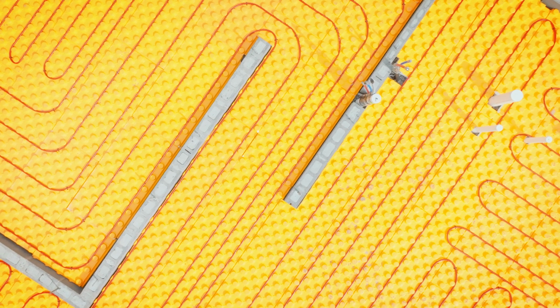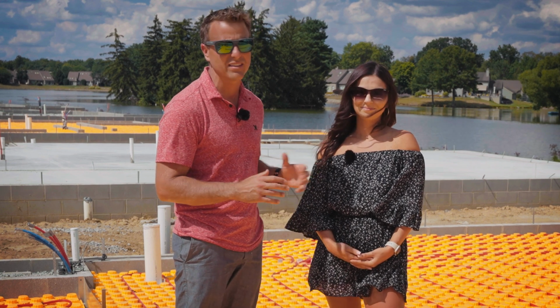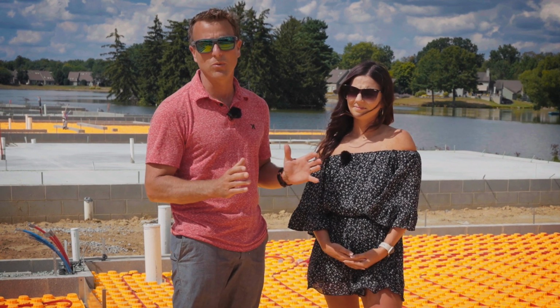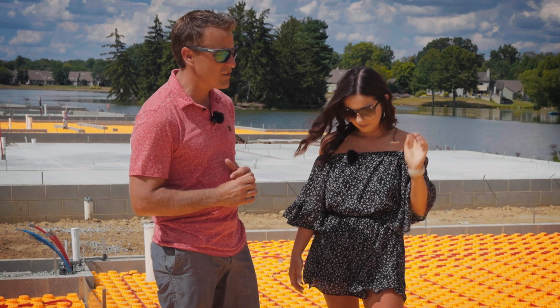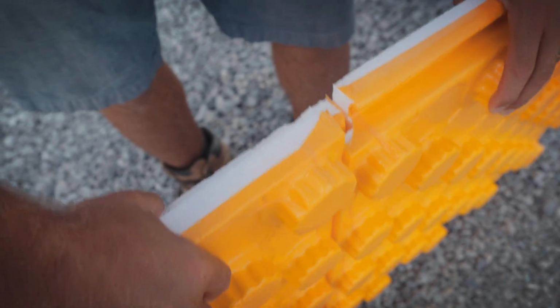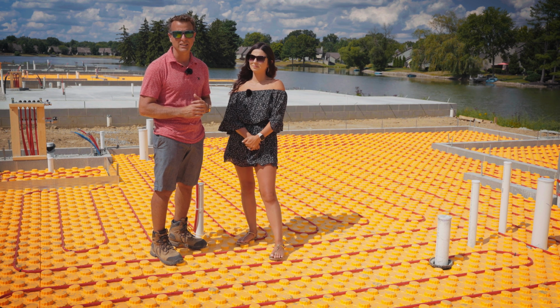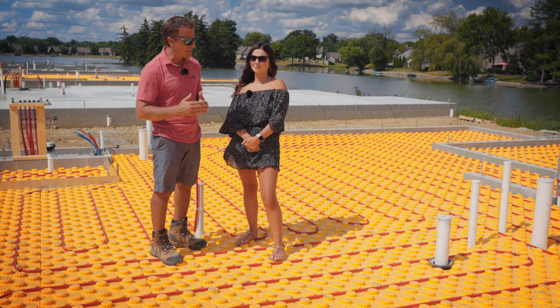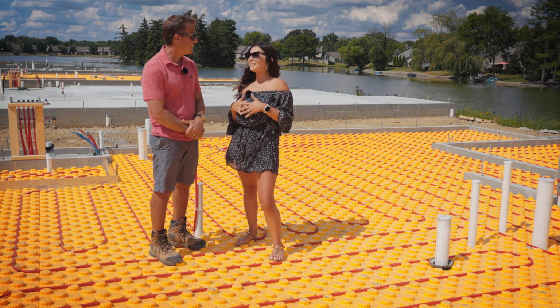Here at Arrowhead One, we have 5 loops, and one of those loops has the master bathroom and laundry room on one zone, allowing us to keep those rooms with comfort year-round. We have about 1,500 linear feet of half-inch PEX tubing on 2-inch Creatherm foam panels, providing a vapor barrier, excellent compression strength, and high-capacity insulation. They actually provide channels as well to keep the PEX tubing spaced evenly. In-floor heating is a complete game changer.